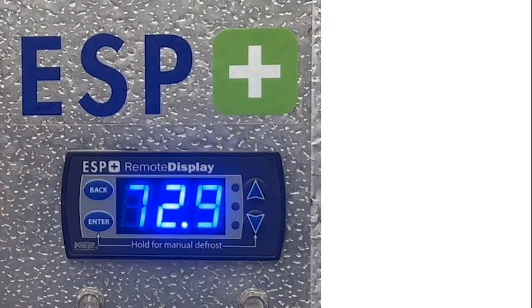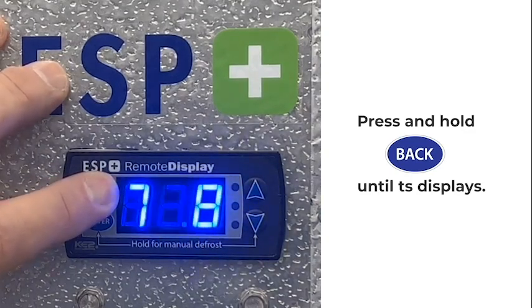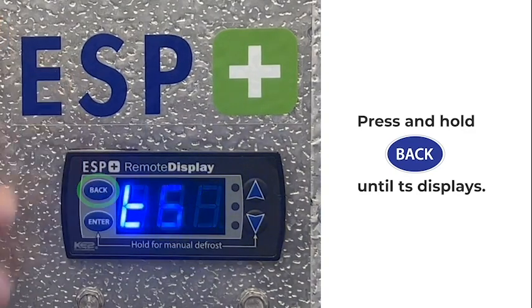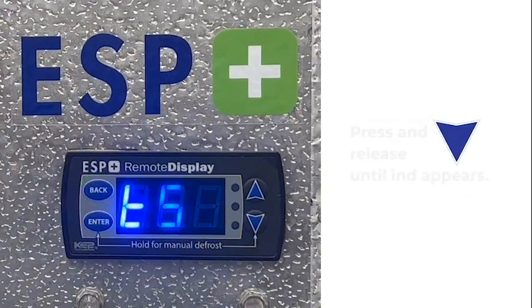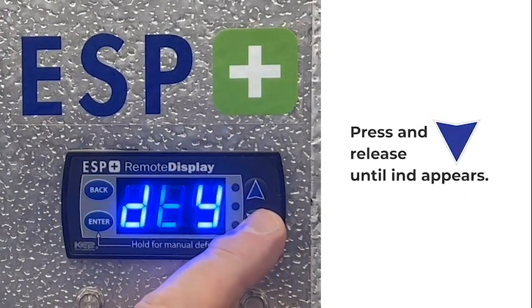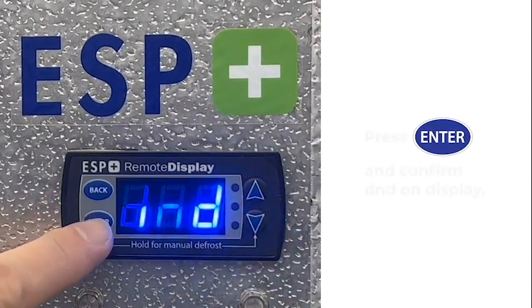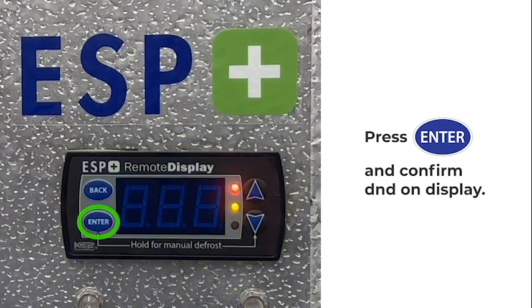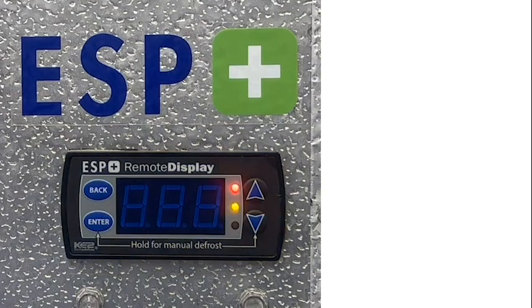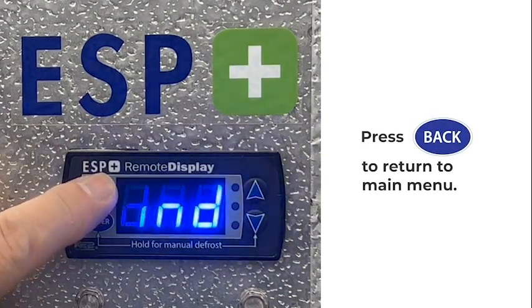The advanced set point menu is accessed by simply holding the back button down until TS, or temperature set point, appears. Once TS appears, push the down arrow until you see dnd. Push the enter button to confirm the demand defrost setting is properly set. Once you've confirmed this setting, push the back button to exit to the main menu.